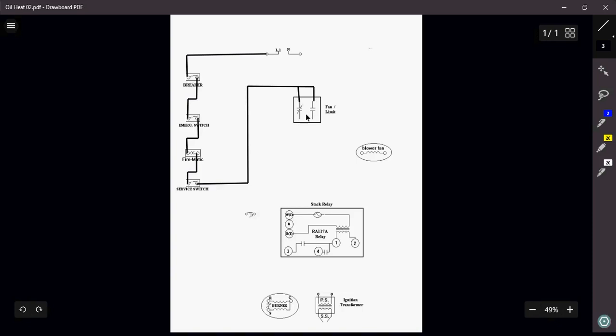This guy here is my limit. This guy is going to open up if the furnace happens to reach an unsafe temperature, probably around 200 degrees or so. This guy here is my normally open. This guy is going to close once the furnace reaches around maybe about 140 degrees, maybe 150 degrees. And that will turn on our blower fan.